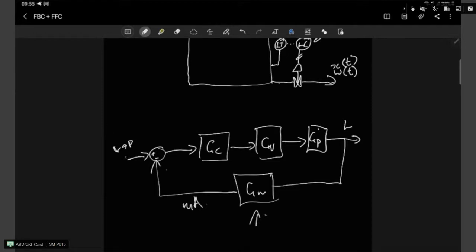There should be another block here, but don't worry about that just now. This we obviously input as some meter value, let's say, so we want it at 2 meters. It converts it to a milliamp signal based on the characteristics of our sensor. Compares these two, let's say we are at steady state, so we get an 8 milliamp signal from that one, 8 milliamp signal from this one. We have our error, which is currently equal to zero. That is zero, so that takes no effect here, and nothing happens.